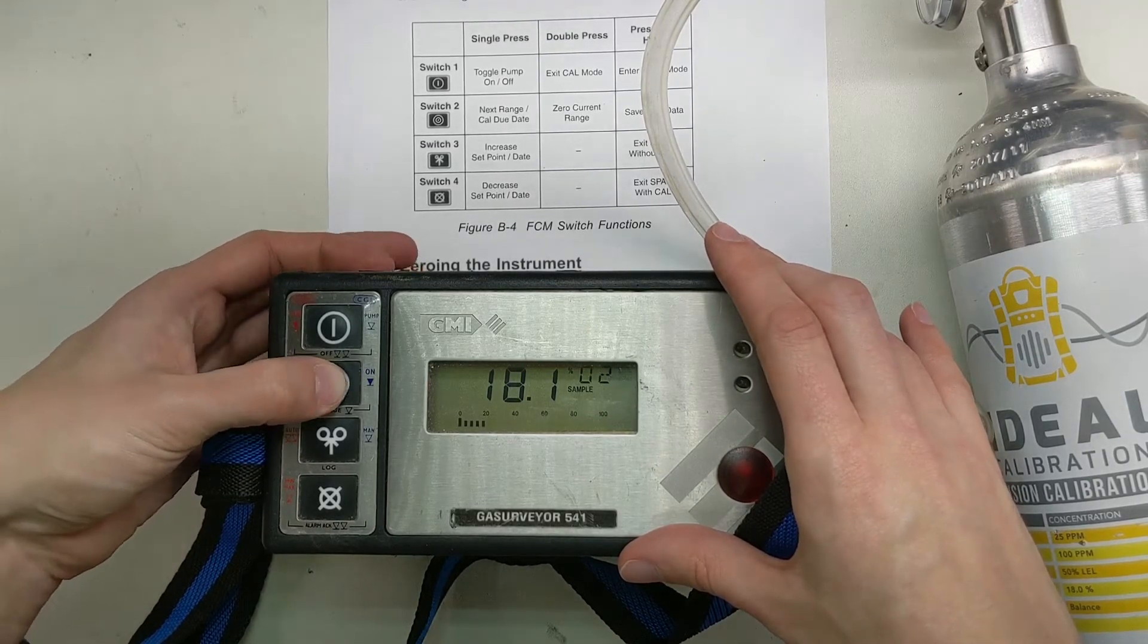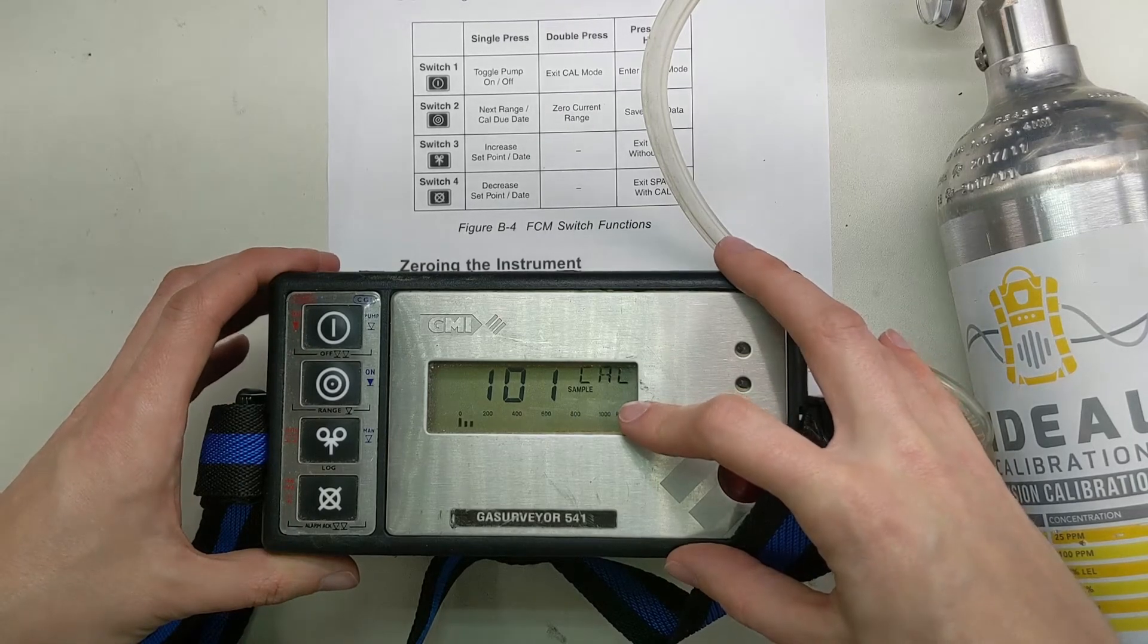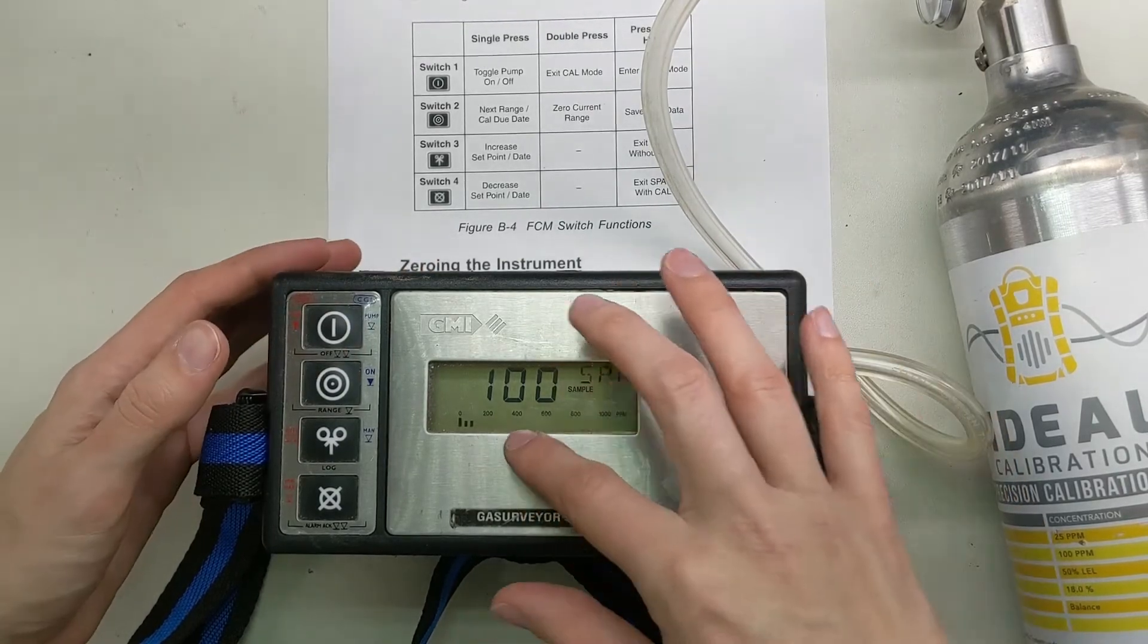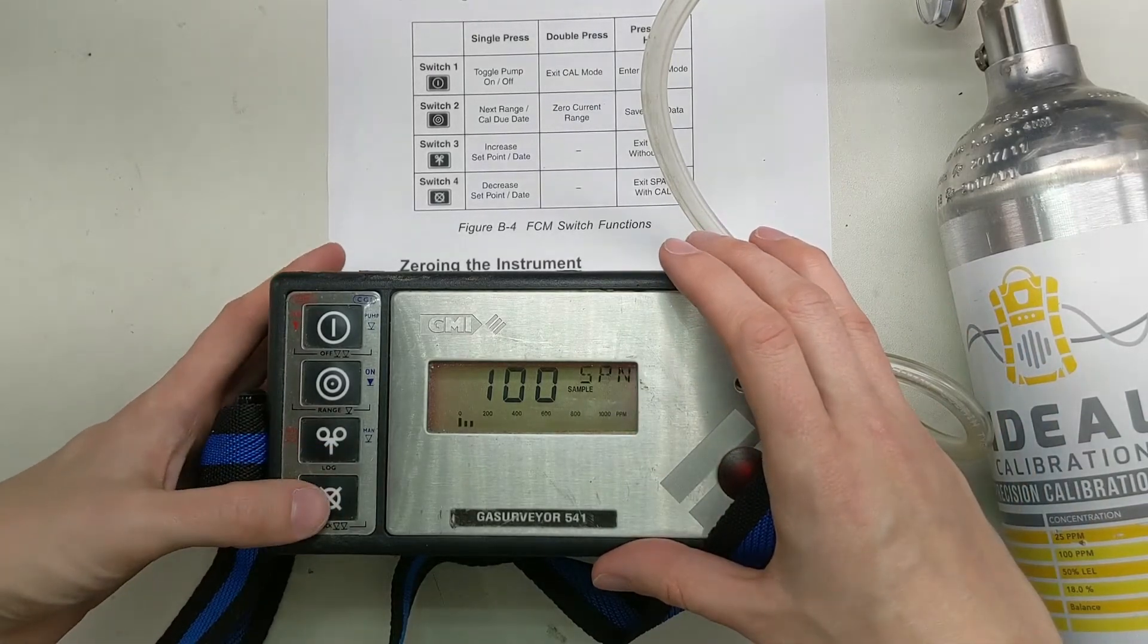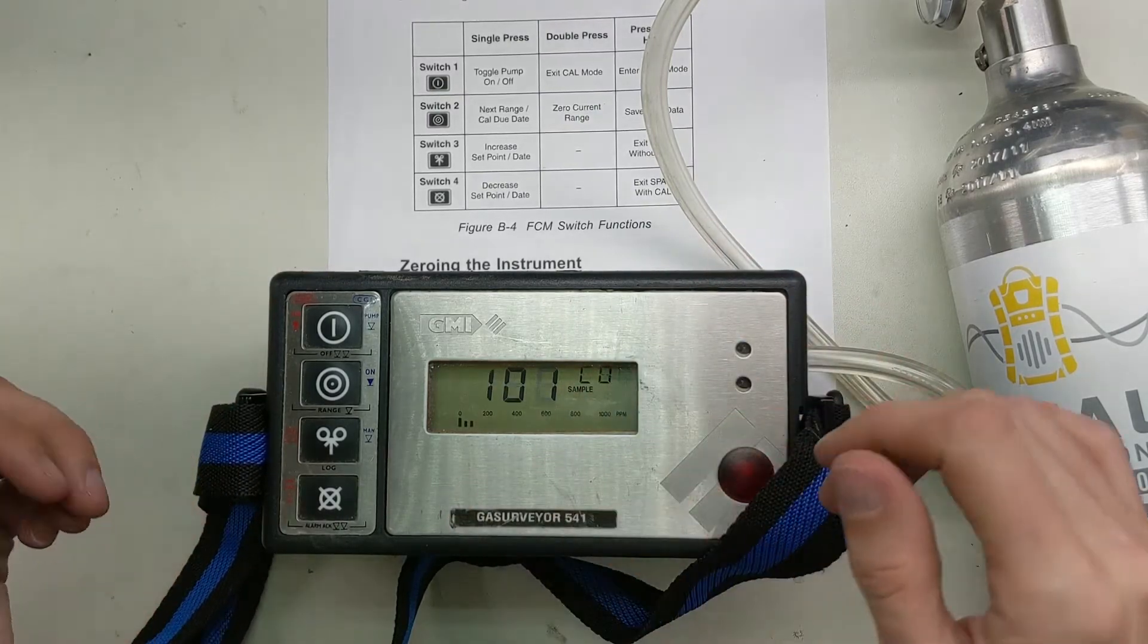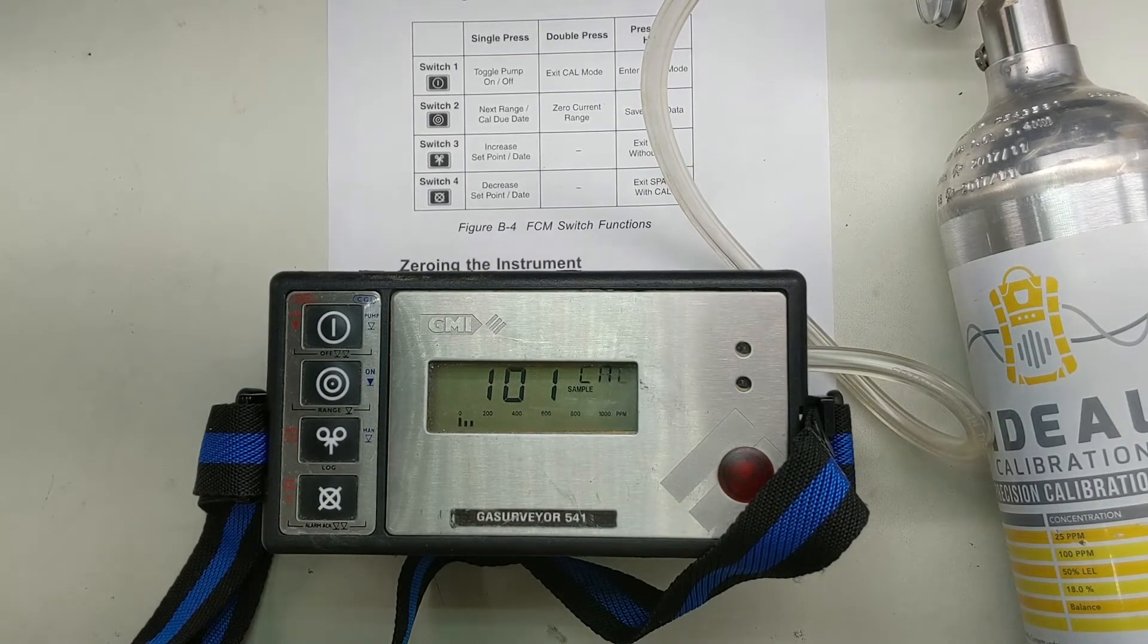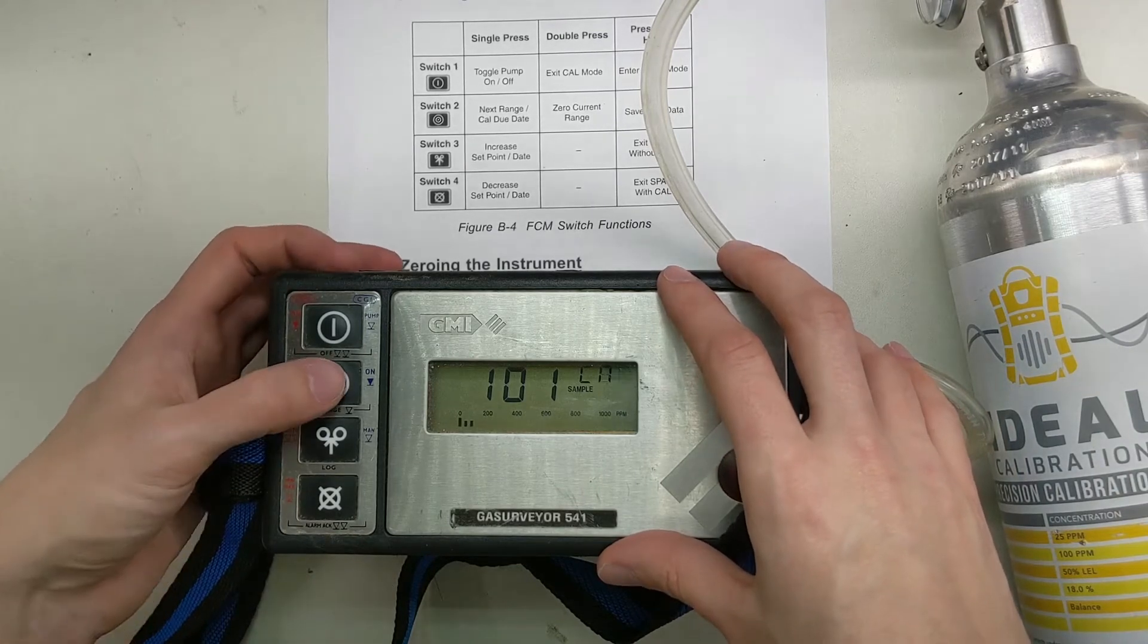Let's move to our next one. We go to next range, press this button once. This is going to bring us to CO. What we're going to do is enter span mode. Looking for 100, that's what we've got. Good deal. We're going to number four, exit span with Cal. It's bouncing right around the 1% range. That's accurate enough for us.